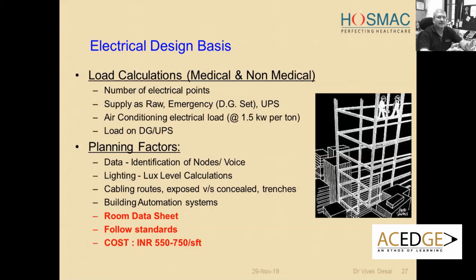Please write that down, I don't think it's written. The room data sheet is something you should do for other buildings also. It tells me how a room will look - it'll be an Excel sheet. So it will say OPD 1, I need 4 plug points, 4 lights, 1 fan, air condition, 1 basin, oxygen suction, yes or no, like that. So when I do this room data sheet for the 1,000 odd rooms in a hospital, it gets me all this data immediately.